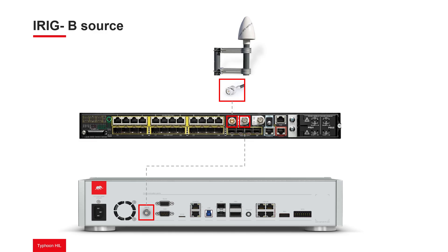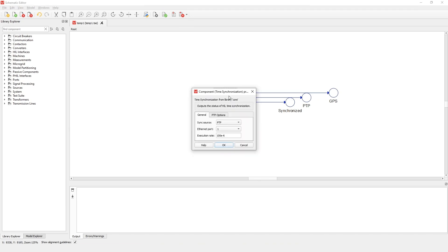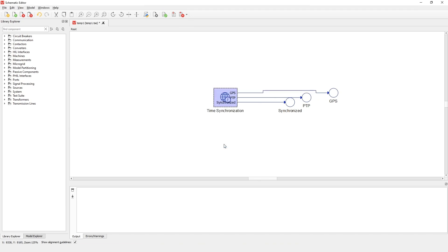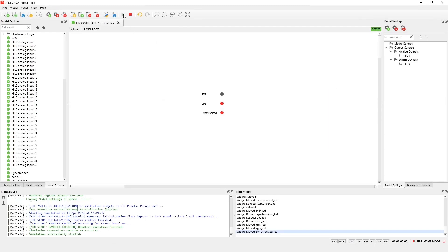Let's now change the source of the time synchronization to iRigB. The HIL device is now connected to a switch over iRigB with a Grand Master device. Now, let's compile the model and run the simulation. GPS status indicates the presence of an external iRigB source. A value of 1 indicates that the system is actively being synchronized. We can see that GPS and synchronized are on, meaning the system is fully synchronized over iRigB.